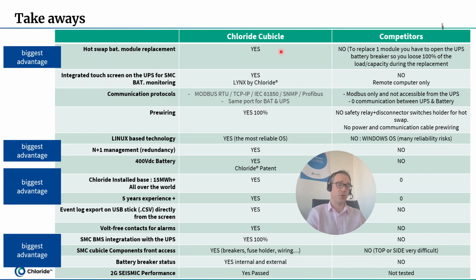I showed you in the previous slide how we manage that with those fuse holders plus the relay to switch off the power inside the battery before any disconnection, to avoid any arc. With our competitors, you will never find this solution. So to replace one module, the risk for you is to have to open the UPS battery breaker, and the risk is to lose 100% of the load and capacity during the replacement.